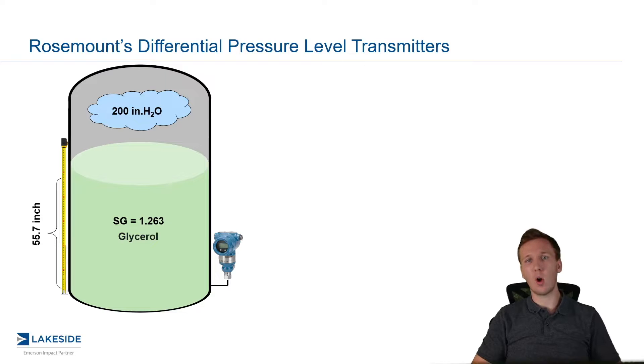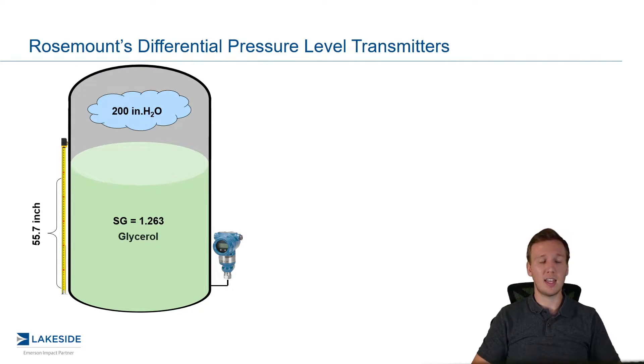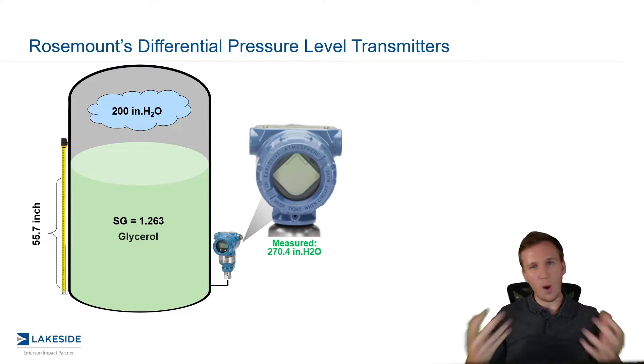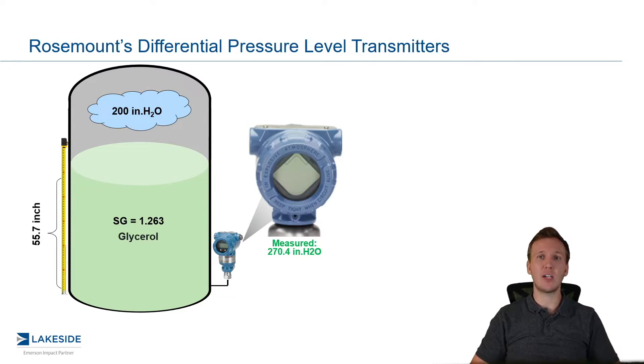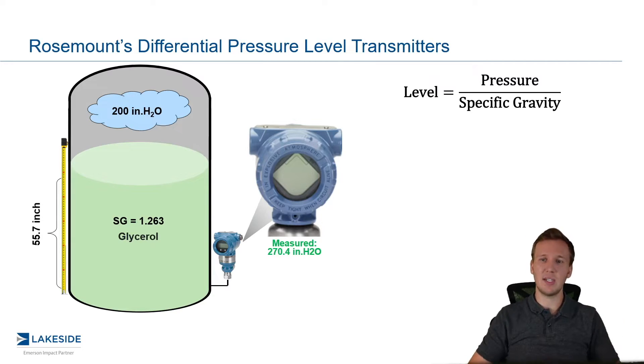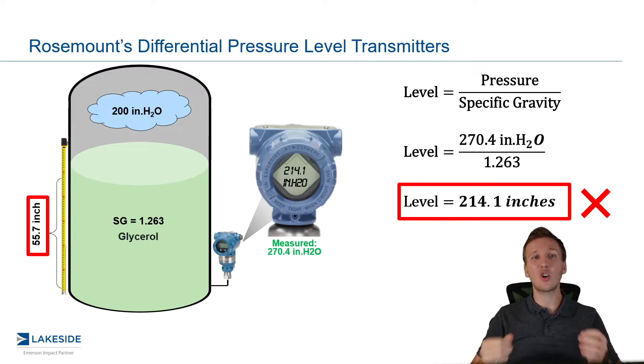Now let's take it a step further and make things a little bit more complex. Let's say we have a vessel that has a closed roof and is pressurized in the vapor space. In this case, we're saying we have 200 inches of water of pressure in that vapor space. Now if we continue to use a gauge pressure transmitter, as pictured at the bottom here, we're going to read incorrectly — we're going to be measuring 270.4 inches of water. This gauge pressure transmitter is sensing the pressure exerted on it from both the liquid and the gas phase, so it's cumulative: the 200 inches of water in that vapor space plus the 70.4 inches of water, which is really glycerol pushing down. So if we continue the same scaling as previously, we take 270.4 inches of water, divide by the specific gravity, and we are left with an incorrect level reading — almost four times the actual product level.